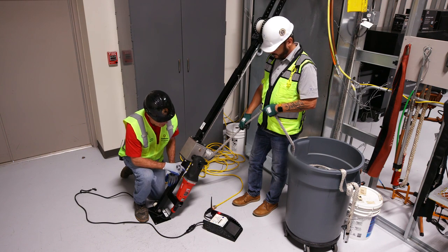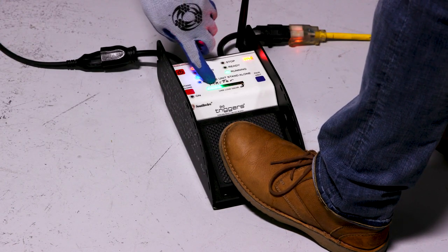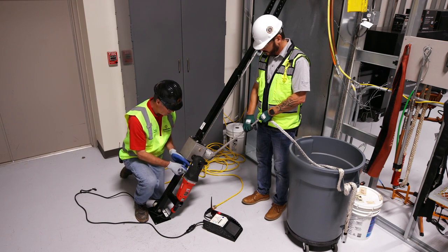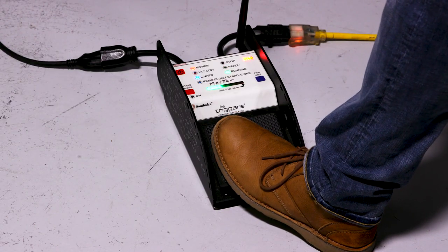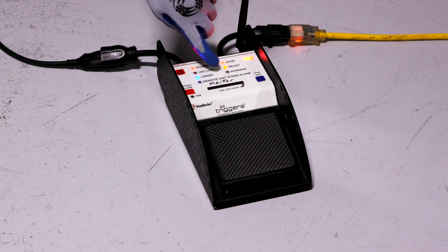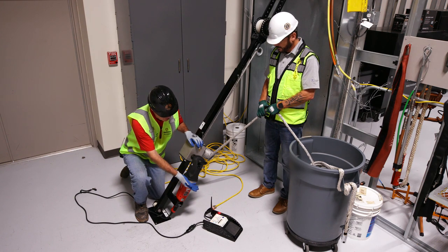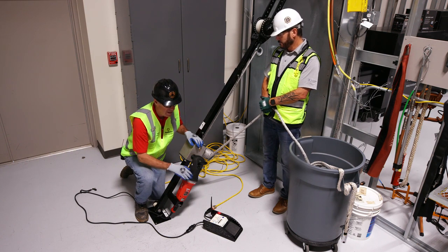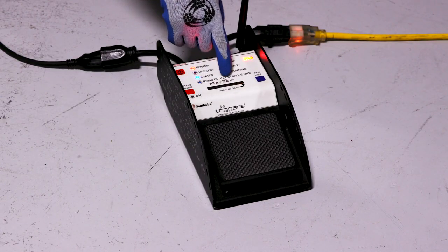We're in high gear right now. We're going to step on the triggers and show you how the lights work. Now we're going to go into low gear, and you'll see the lights in low gear. When the lights get all the way to the end, that's when you go from high gear to low gear. If you're already in low gear, it's just going to max out at that point. We have used these triggers to where the actual puller has stopped pulling and we did not fry our motor — it just stopped and everything was fine. That's what the lights are for: to go from high gear to low gear.